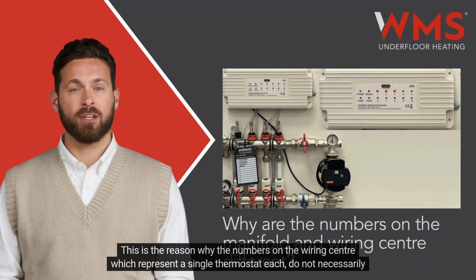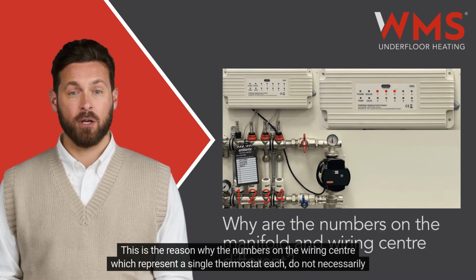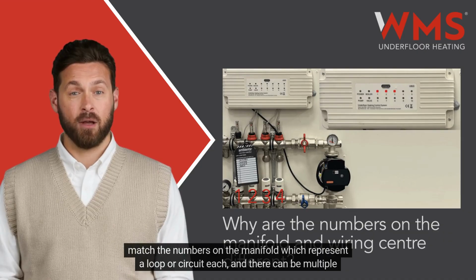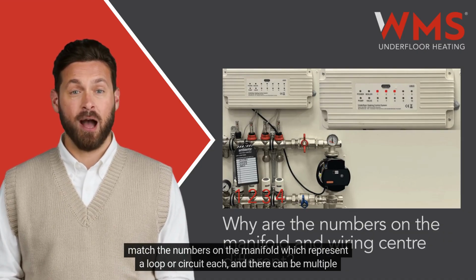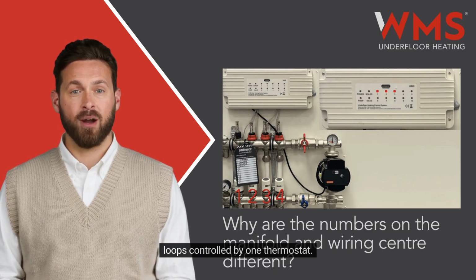This is the reason why the numbers on the wiring center, which represent a single thermostat each, do not necessarily match the numbers on the manifold, which represent a loop or circuit each. And there can be multiple loops controlled by one thermostat.